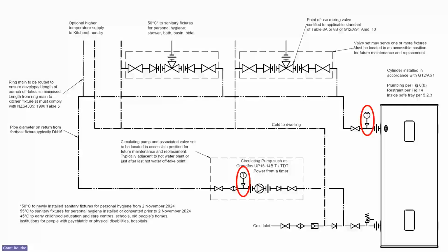It's best done on small systems by installing Pete's plugs. You can then insert your temperature probe right into the middle of the flow. We go to lots of ring mains where we see T fittings and nipples and then a temperature gauge, and the temperature gauge is 100 millimeters or more from the actual water flow, and it doesn't give a reliable indication of what the temperature flow is.